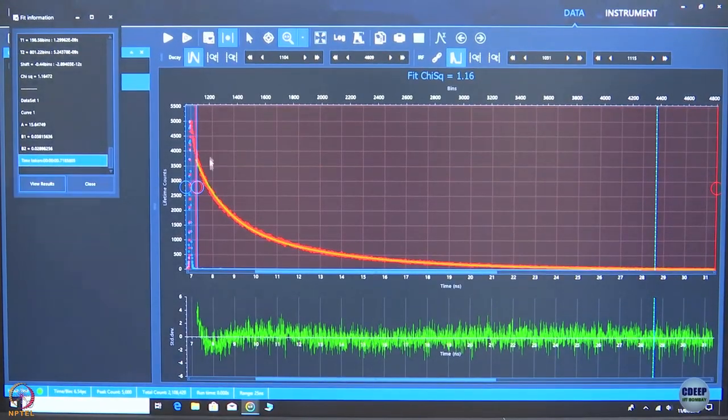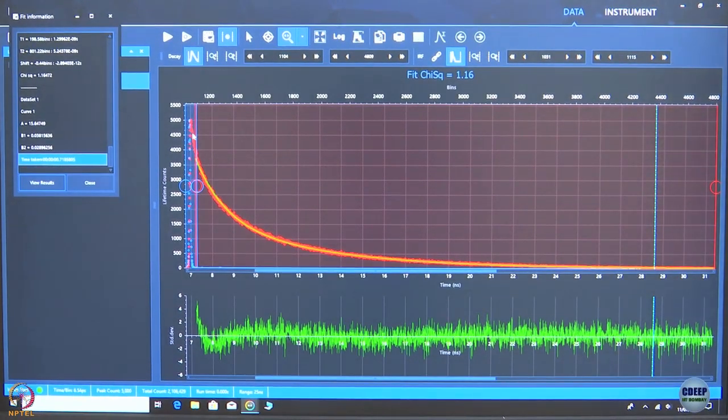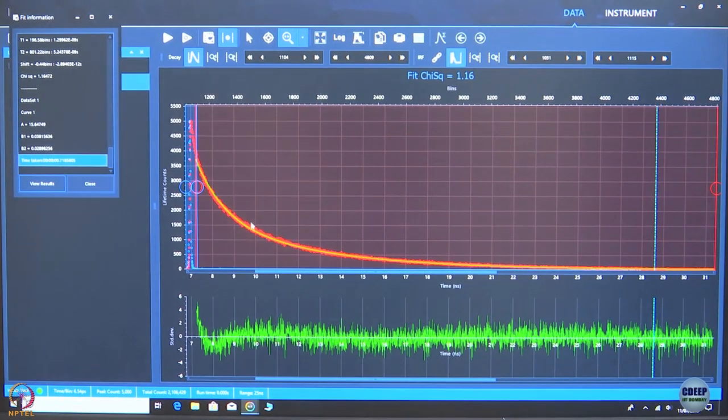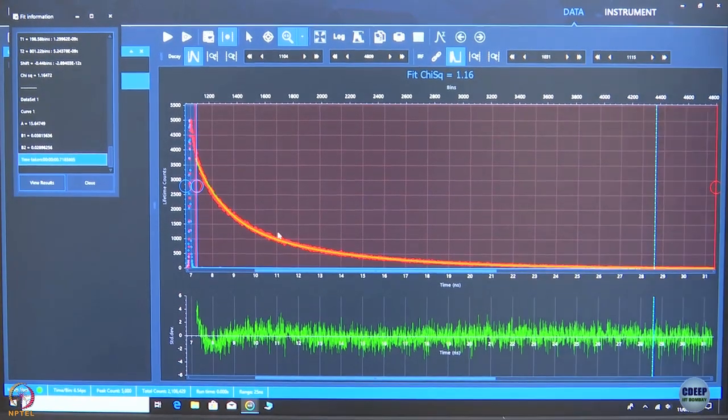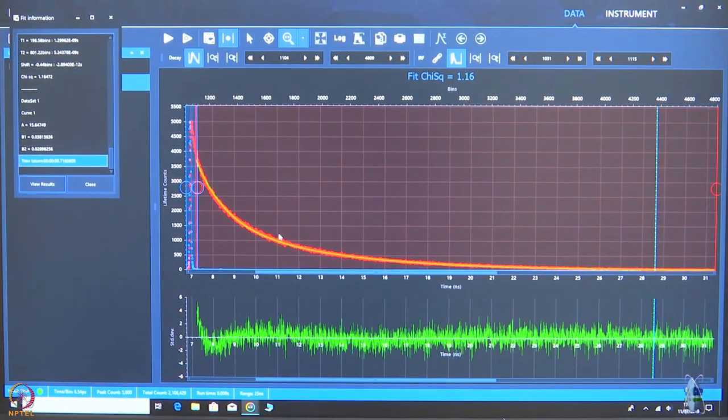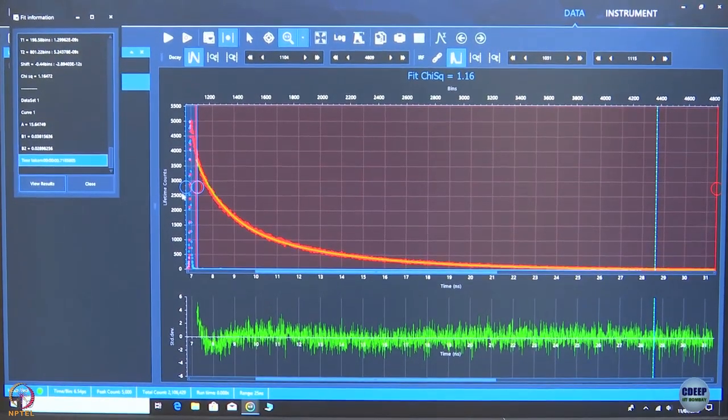Right. So what you see here is the result of fitting this decay to a bi-exponential function. So this range, denoted by the two blue lines, is the range that we have set for the instrument function. Essentially, if you remember, for getting the intensity at each of these points in time t, we had to integrate the fitting curve multiplied by the instrument function at time t minus t dash, over 0 to infinity or minus infinity to plus infinity. Here, for all practical purposes, you want to set a limit within which the instrument function has non-zero values, and this is the range that we have set.